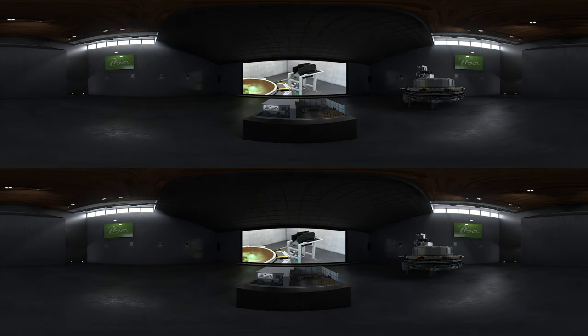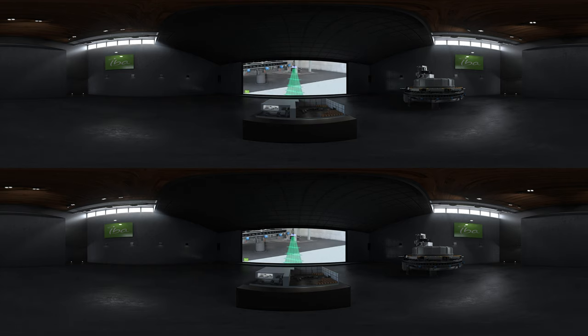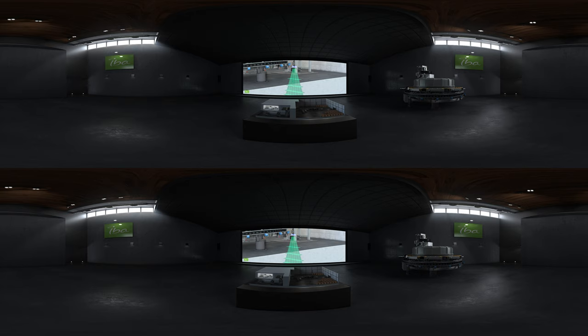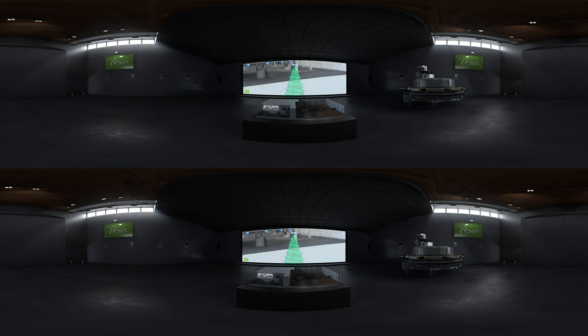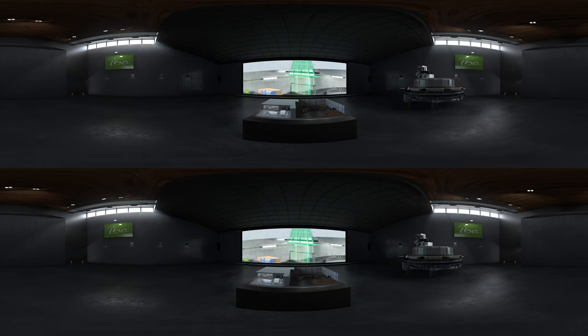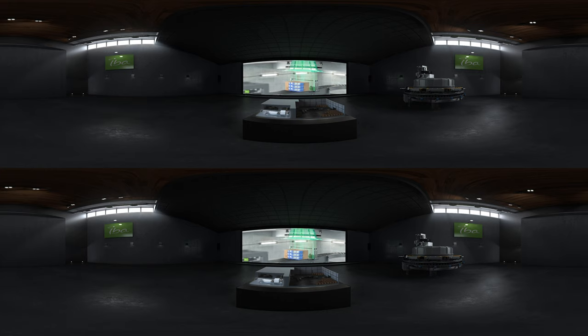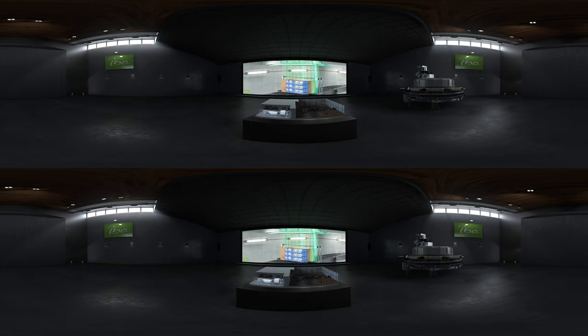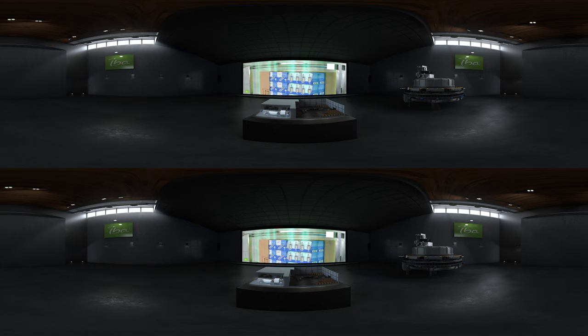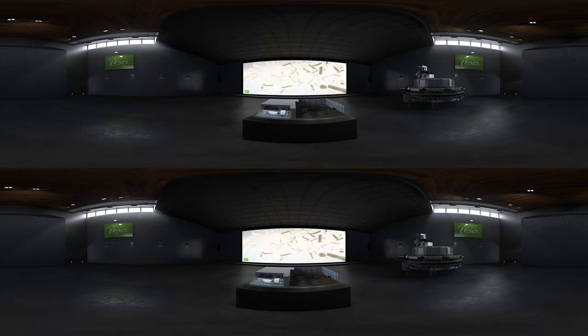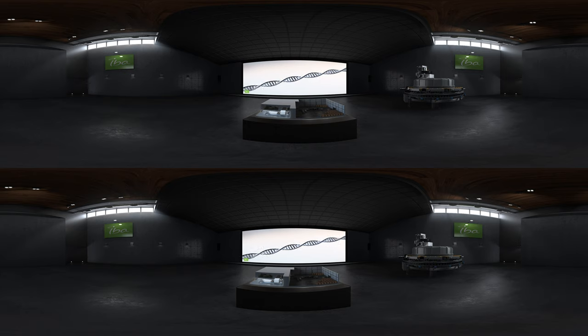The beam line transports the electrons up to the product to be irradiated. The 270 degree magnet bends the electrons. The electron beam is then diverted in the scanning magnet to create a curtain of electrons going out of the scanning horn to irradiate the entire boxes of products. When passing under the beam, the boxes are irradiated and the DNA of the bacteria included in the products are damaged by the electrons, preventing them reproducing themselves.